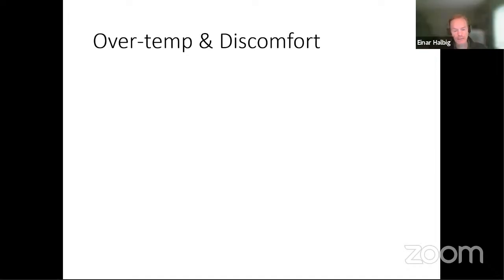Yeah, so I'll just add to that quickly. Hot 2000 doesn't give you any warning that temperatures are climbing. The energy advisor has to know where to look in the results to ascertain that, based on the available information out of the energy model. And it also doesn't look at situations on a room by room basis. It looks at the whole building numbers. So it won't give you a warning, and even if you're looking for information, you won't necessarily get it about how much a particular room potentially overheats, or how much free heat energy that particular room gets.